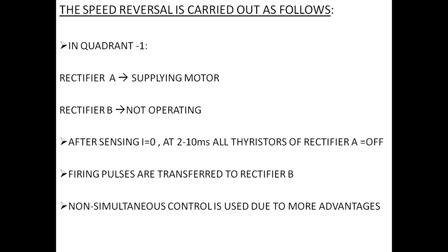From now onwards, we use a technique called current control loop adjustment. This current control loop adjustment is done in the firing angle alpha B continuously, because we have to brake the motor at the maximum allowable current. This maximum allowable current is used to brake from the initial speed to zero speed, and then the motor accelerates to the desired speed in the reverse direction.